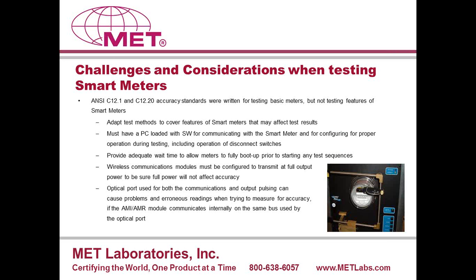Okay, some of the challenges and considerations when we're testing smart meters. The ANSI standards, the C12.1 and C12.20, were written for the meters themselves, the electricity meters and the accuracy of the meters themselves, and any environmental test trying to affect the accuracy of that meter. But the standards were not written for the smart meters that we see today.